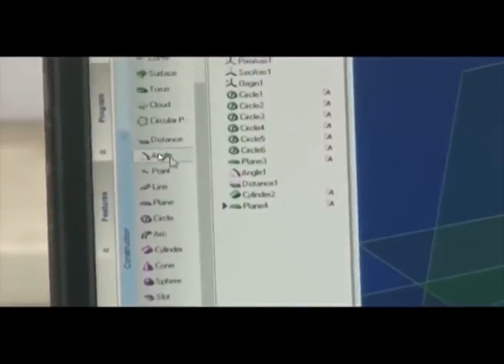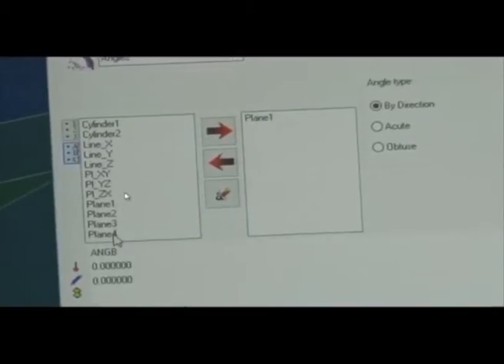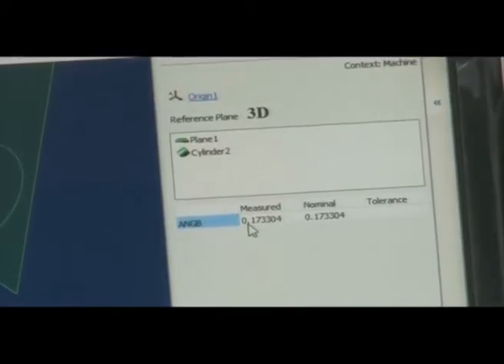We go to Construction and select Angle. The angle is selected between Plane 1 and Cylinder 2. We click OK and Yes. What should be the angle between this cylinder and this plane? The angle should be zero. The software reports the angle as 0.173304 — quite close to zero. So this angle is effectively zero, confirming the cylinder is parallel to the plane.